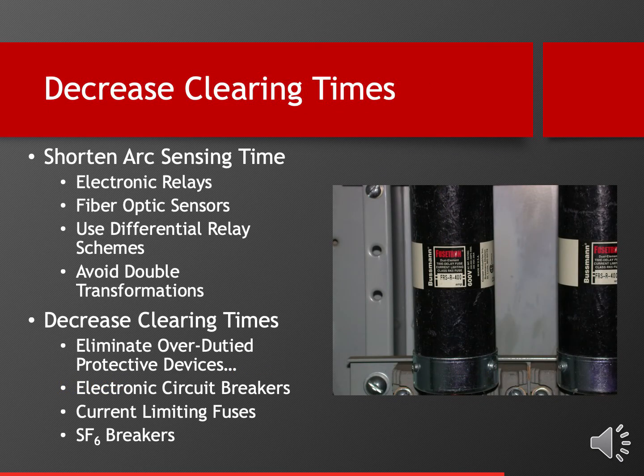Decrease clearing times. Well, there are several things we can do, and I don't want to go into the engineering weeds too deeply here. But in terms of shortening the arc sensing time of the arc time continuum we talked about earlier, one thing we can do that really improves our situation is to use electronic relays. If you have breakers, if the system is critical enough to do this, electronic relays are often much faster than thermomagnetic relays. And in those situations, we'd want to use those if we could. So using electronic systems are faster than other mechanical systems.